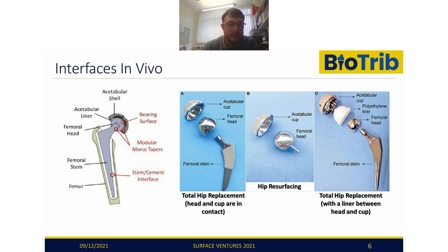But then we also have a series of other components where we have a femoral head, typically made from cobalt chrome or maybe ceramic, some alumina based ceramic, and then an acetabular cup which goes in your pelvis, which again can be, you know, metal on metal articulations still do exist, and they're still put in by some people that believe in that technology. With all respects, it works well in certain demographics. But this could also be polyethylene or ceramic as well.